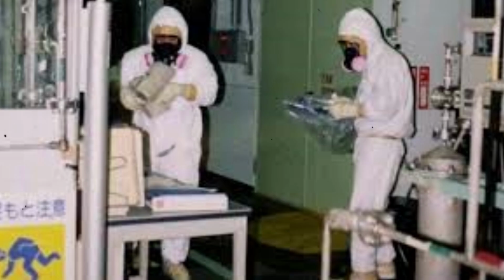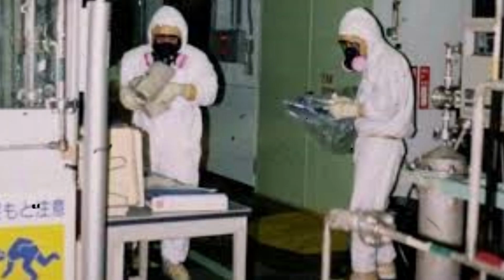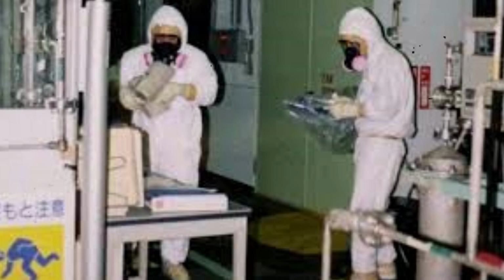These connections were designed for building fire suppression, not reactor vessel injection, creating uncertainties about flow rates, pressure capabilities, and system compatibility under emergency conditions. The effectiveness of seawater injection into damaged reactor cores involved complex thermal hydraulic phenomena that could not be accurately analyzed without detailed knowledge of fuel debris configuration. If fuel assemblies maintained relatively intact geometry, seawater cooling could provide adequate heat removal to stabilize temperatures below further damage thresholds.